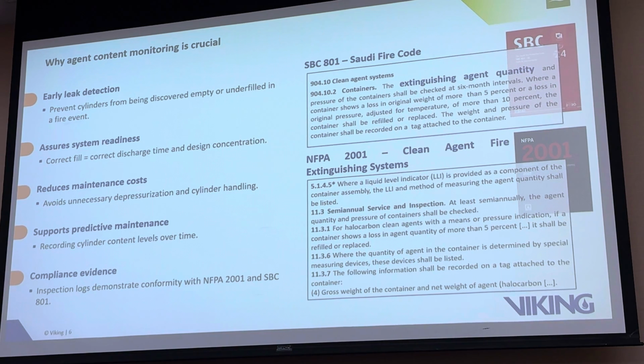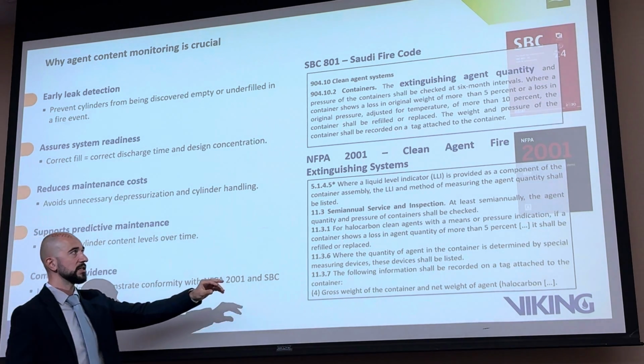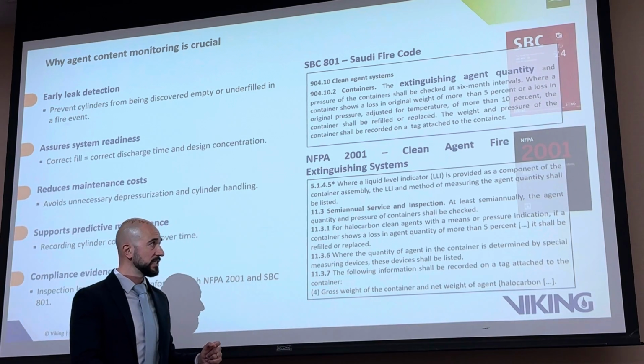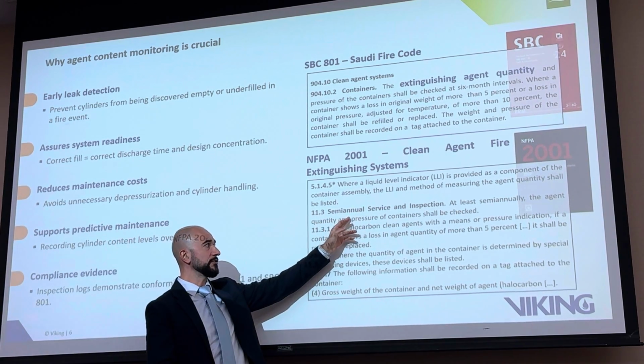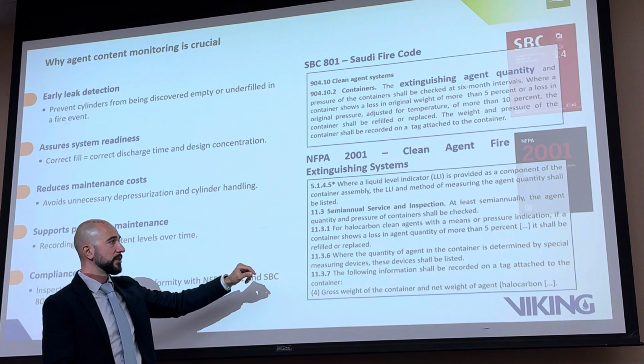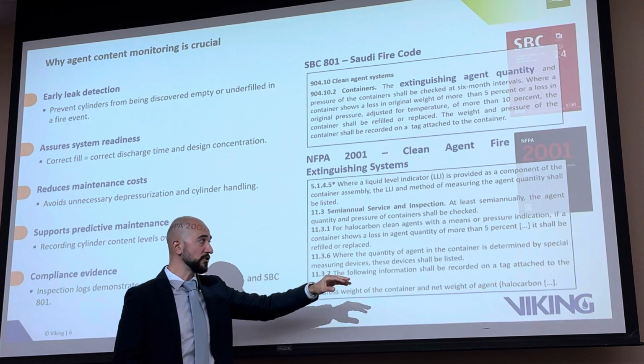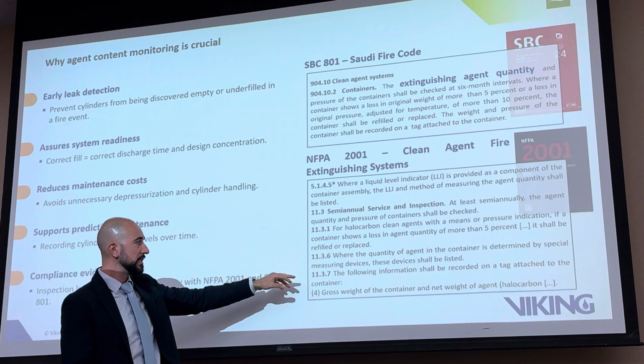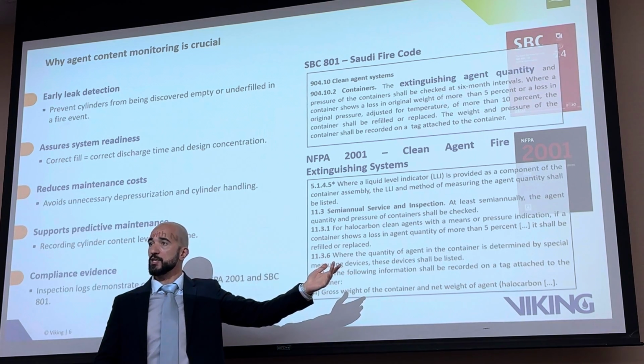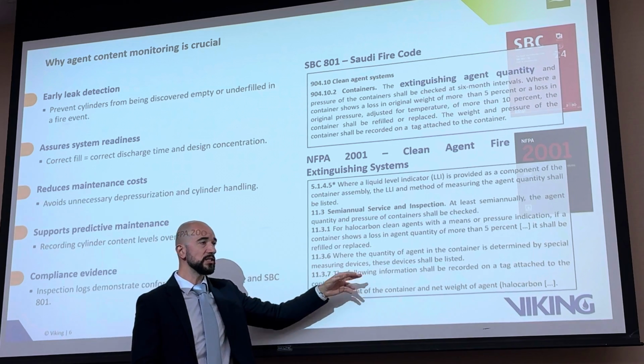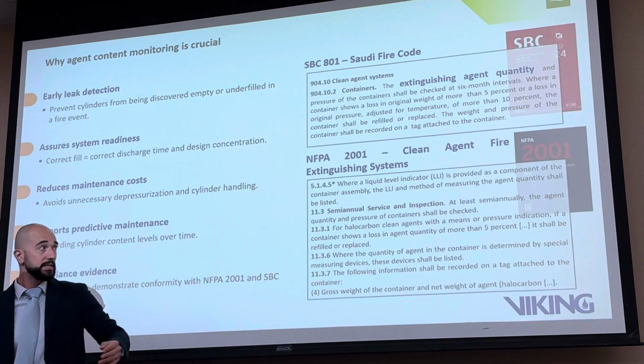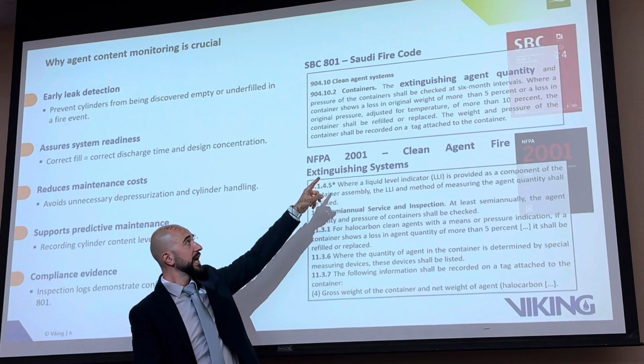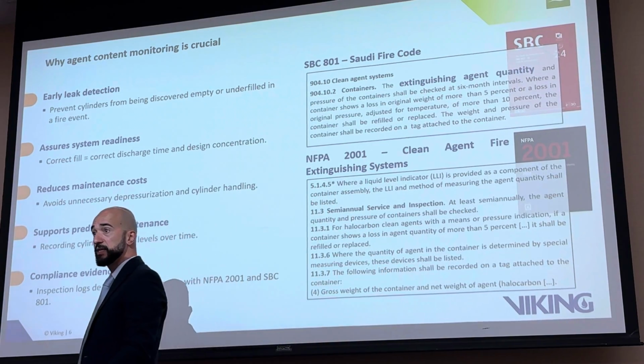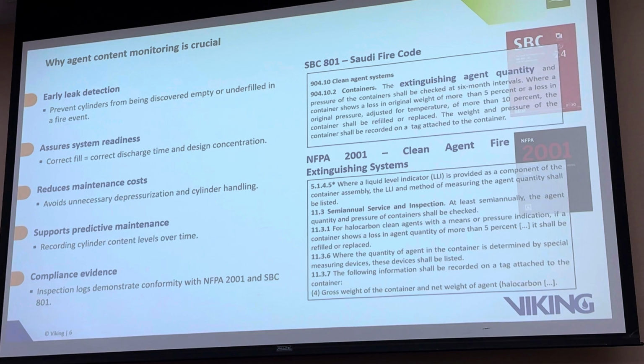The NFPA 2001 has a number of clauses that I have extracted that likewise, they say you may use a liquid level indicator, right? You need to do semi-annual service and inspection. There's a maximum of 5% leakage that you may allow, right? The device has to be listed, that's why the ULLA is FM approved, and the information needs to be recorded over time. And this is actually a requirement both of NFPA and recorded according to SBC. So you need to take record of what is the content of agent over time, right? So this is the code.